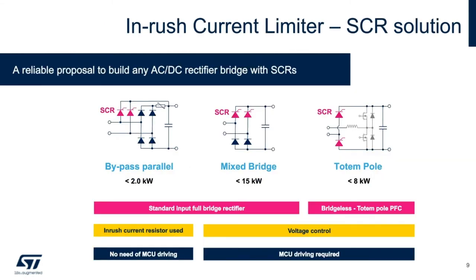There are several implementations of SCRs for inrush current limiting that can benefit a power supply, depending on the topology, power level, and control complexity. The simplest method is the bypass parallel configuration, useful to power levels up to about two kilowatts, with benefits of simple self-driving control but still using a series resistor to limit the initial inrush current. More complex solutions, such as the mixed bridge with SCRs or SCR-controlled totem pole PFC, can eliminate the current limiting resistor altogether but require a microcontroller to implement smart algorithms. Much higher power levels can be optimized with these topologies, and we'll touch on all three.